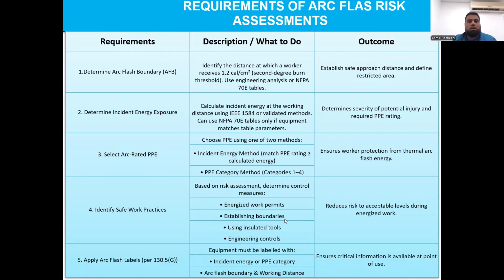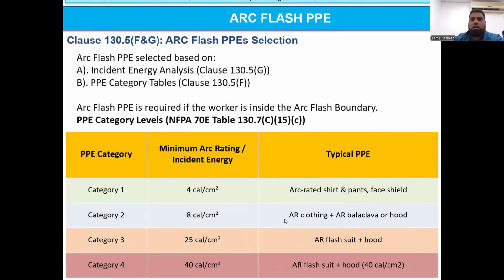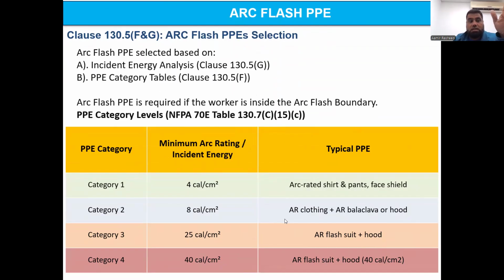And then you have SOPs, safe working practices, safe operating procedures, like a permit to work system, that is how you are going to do it. Any kind of engineering control reduces risk to an acceptable level during the energized work. Apply arc flash labeling, so critical information is available whenever they are working. If someone is working near energized equipment, the information is next to it, labeled there, so that you can understand what kind of hazard is there. So these are arc flash PPEs, basically based, as I said, on incident energy analysis as well as the PPE category table. These are two.